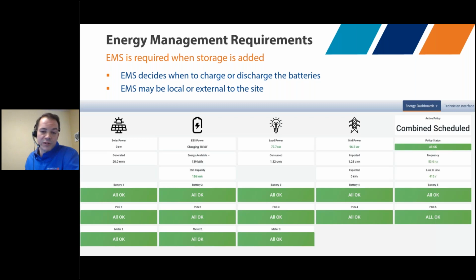This can do things such as PV smoothing. If you have a grid and a solar array, and a cloud passes over causing a sudden loss in power, you want the EMS to step in and discharge the battery in order to smooth out the slew rate of the power. Or if you're doing demand charge management, you want the EMS to monitor the AC meters on the load side, and if you get a peak in the amount of power being drawn, the EMS comes in and asks the battery to discharge in order to shave that peak.